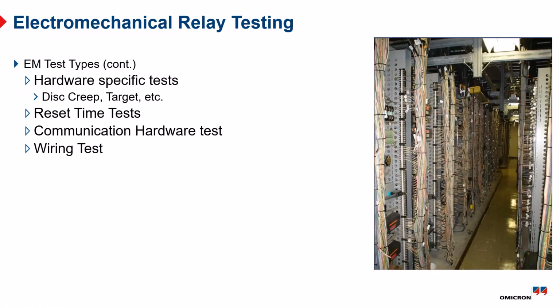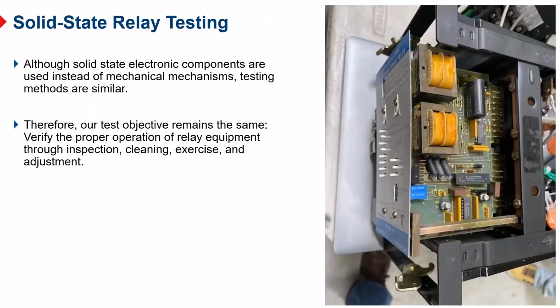I talked about that hardware specific test. There were some other tests, reset time test, and then of course carrier communications equipment that would have to be tested pretty much separately because they're a separate box in the panel. And then of course the wiring test. And this aisle there, I don't remember exactly where that was, but I took that picture at some point during my field career. You can see the electromechanical relay panel. So the wires going to and from the CTs, PTs, and breakers come in here to what we call the field terminal blocks along the edge here, and then the relays are mounted in the panel, and then you have some switchboard wire that goes from the terminal blocks onto the back of the relay.